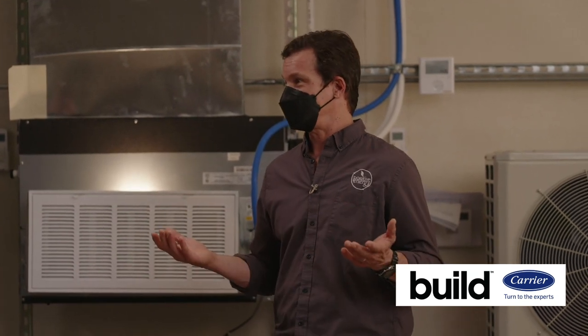But then all these capacities we just talked about, so 6,000 BTUs an hour is a half a ton. That is at AHRI rating conditions, right? So that's 95 and 80. So it's not when it's 100 out or 90 out, it's 95, and 80 inside. So if you keep your house at 72 and it's 100 out, that half-ton system isn't going to give you a half a ton. Conversely, if you were keeping it at 80 and it was lower than 95 out, it would be more than a half a ton.